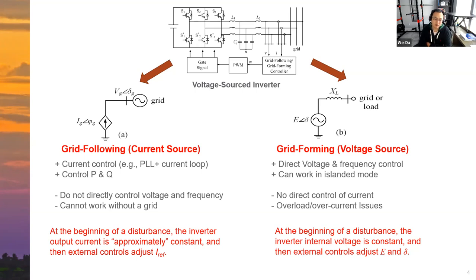The left side is called grid following control. Today, more than 99.9% of grid-connected inverters use this grid following control to operate in the bulk power system. Basically, they make the voltage source converter approximately behave as a current source. They use a current control loop and a phase-locked loop to control the magnitude and phase angle of the current injected into the grid.